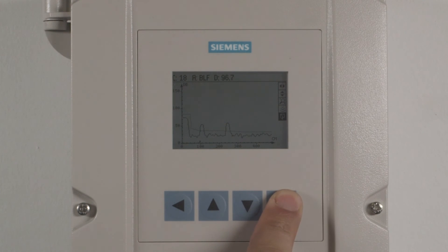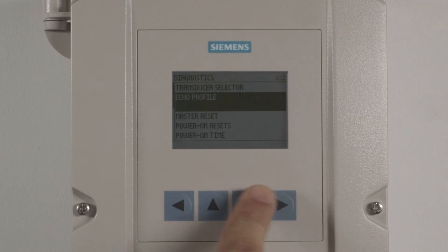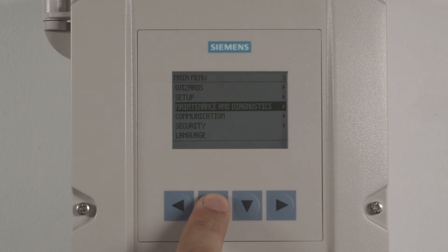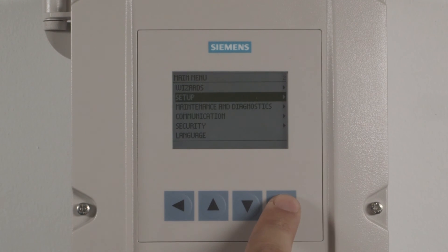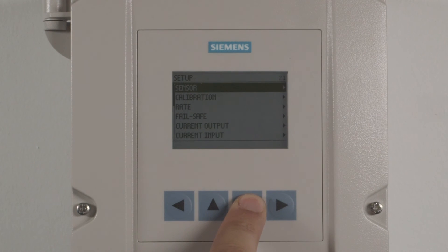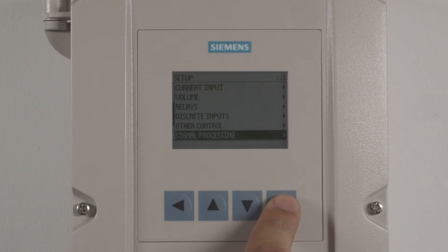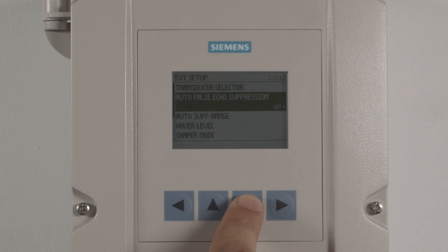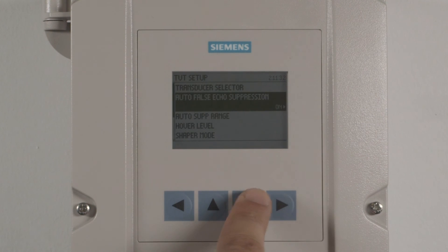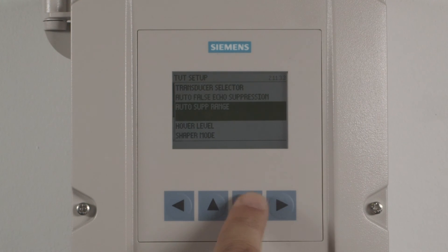To begin, exit the echo profile screen. Press the left arrow twice to return to the main menu. Highlight setup and press the right arrow. Highlight signal processing and press the right arrow. Highlight TVT setup and press the right arrow. Highlight auto-false echo suppression and press the right arrow. Highlight on and press the right arrow. Scroll down to select auto suppression range and press the right arrow.